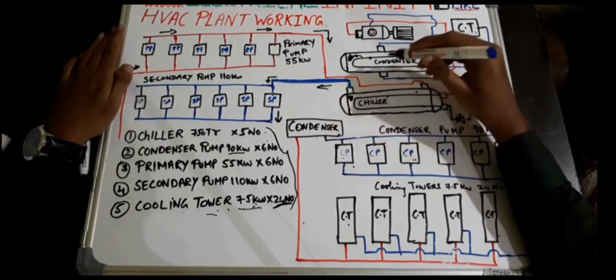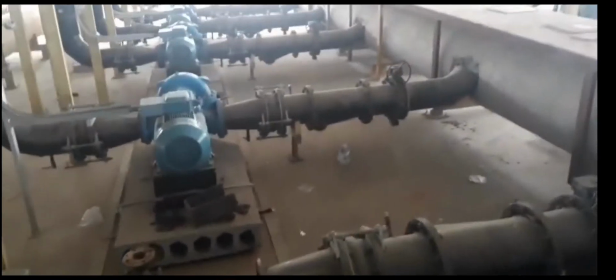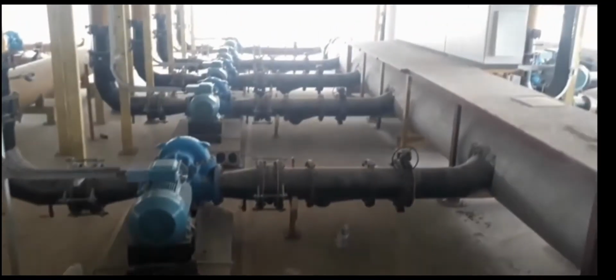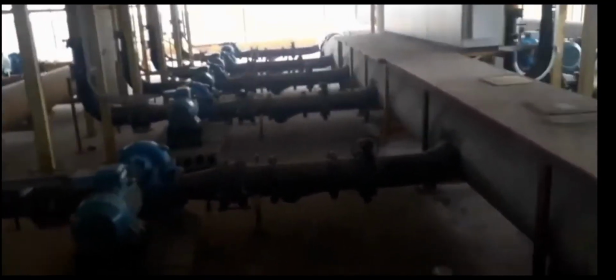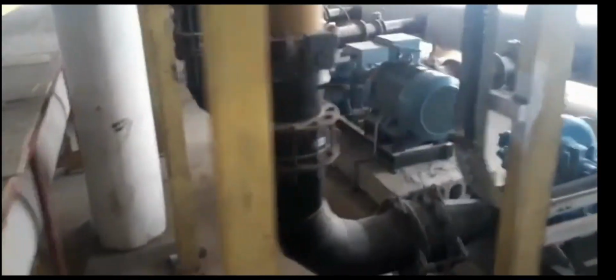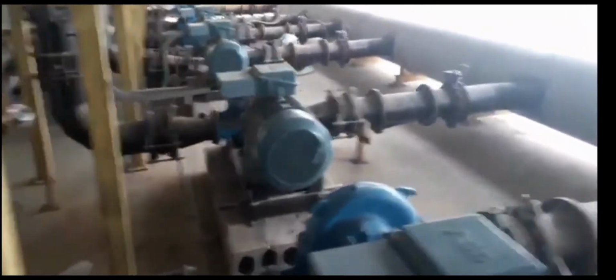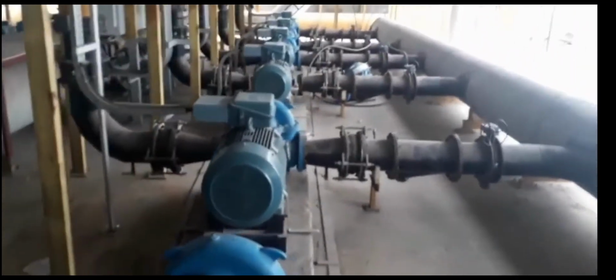the shell type. So here we have a primary pump after a condenser pump, and these primary pumps are each of 55 kilowatt, and we have used 6 primary pumps here for pumping of hot water from the building. And proceeding further, here you can see these are secondary pumps, each of 110 kilowatt, for pumping of cool water into the building.